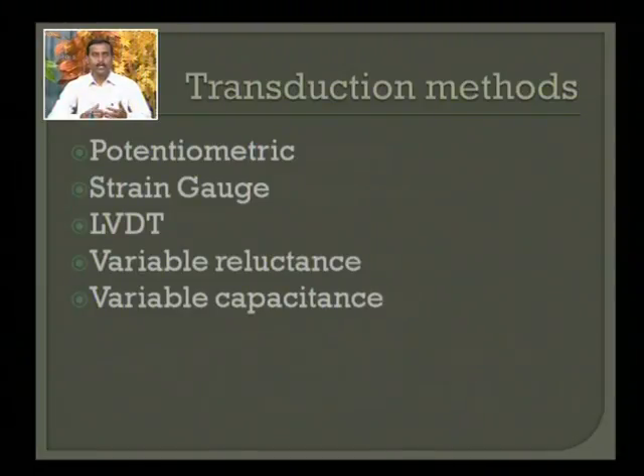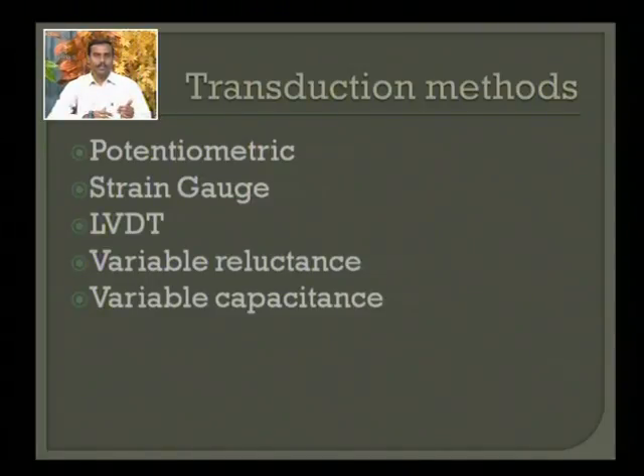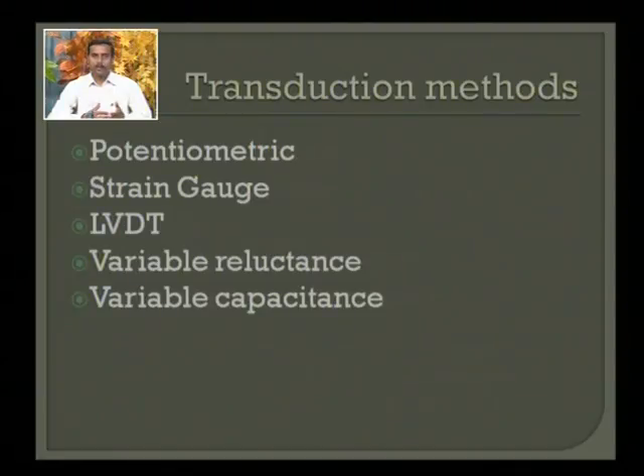Another method is connection of a strain gauge: bonding strain gauges at different locations on a diaphragm, capsule, or bellow means that the strain generated by the applied pressure changes the resistance of the strain gauge, and that difference of resistance can be measured using a Wheatstone bridge to give an electrical output. An LVDT (variable reluctance type) can also be used — the LVDT core is connected directly to the displacement device like a diaphragm or bellow, and the displacement generates a differential output from the LVDT. Variable reluctance or variable capacitance devices are also options for converting displacement due to pressure into an electrical quantity.